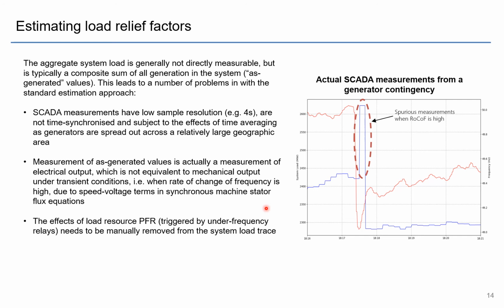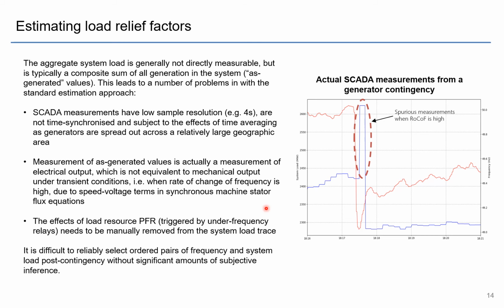Also, the effects of load resource PFR, things that are triggered by under frequency relays, need to be removed from the system load trace, because that is not considered load relief, it is considered PFR. So in conclusion, it's quite difficult to reliably select ordered pairs of frequency and load values during a disturbance. It's hard to find anything between here and the nadir point. Most of the time it's subject to a lot of human subjectivity and inference.